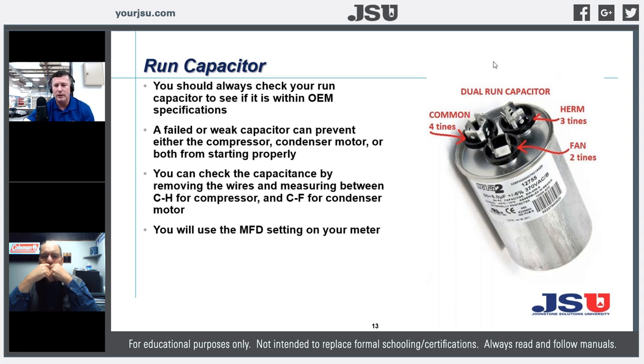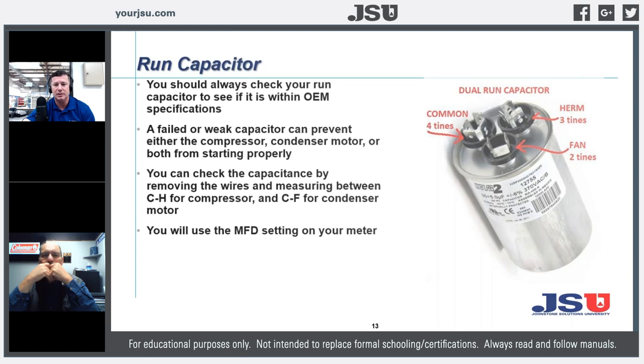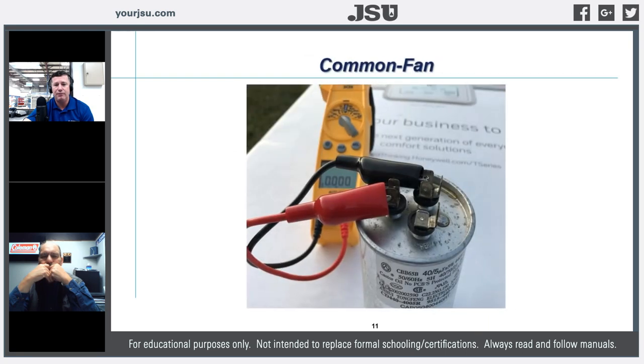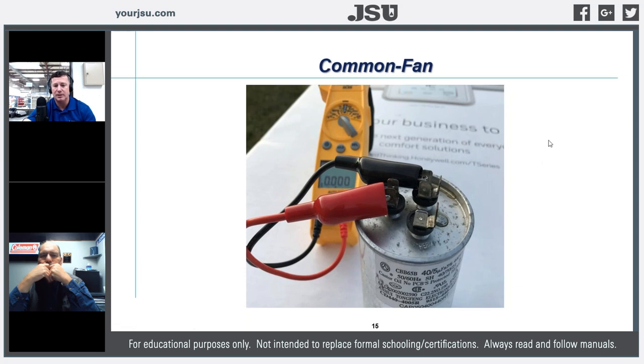A weak capacitor will affect the starting of a motor because it's not providing potential energy to the start winding. We can test our capacitors from common to Herm and from common to fan. The capacitor label tells us the tolerance for that particular unit — for example, a 40+5 rated at 440 volts with plus or minus 5%. If it's outside that 5% tolerance on either rating, the capacitor needs to be replaced.